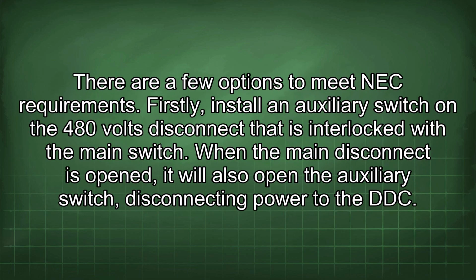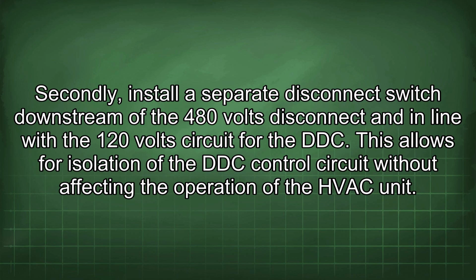There are a few options to meet NEC requirements. Firstly, install an auxiliary switch on the 480 volts disconnect that is interlocked with the main switch. When the main disconnect is opened, it will also open the auxiliary switch, disconnecting power to the DDC. Secondly, install a separate disconnect switch downstream of the 480 volts disconnect and in line with the 120 volt circuit for the DDC. This allows for isolation of the DDC control circuit without affecting the operation of the HVAC unit.